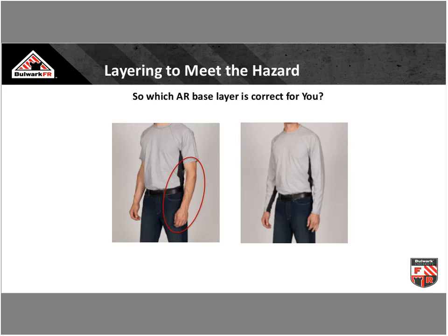Now, depending on your hazard assessment and your training, could I implement a short sleeve base layer and still take the benefit? Yes, if you were a rubber sleeve utility worker. By putting the rubber sleeves over top, you cover from shoulder down to fingertip, so your system would be chest down. You wouldn't need to worry about the single layer because your primary protection is those rubber sleeves. That would be the only way you could implement a short sleeve base layer and still get the benefit of the tested results at 18. I've heard that argued—I'm not really sure where I sit on it, but I understand what they're saying. I get it.